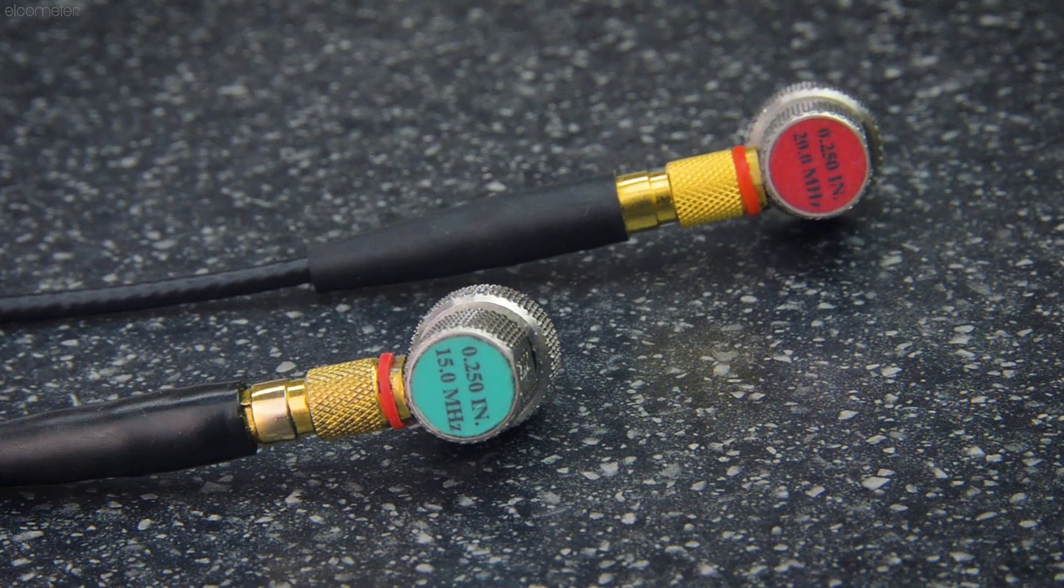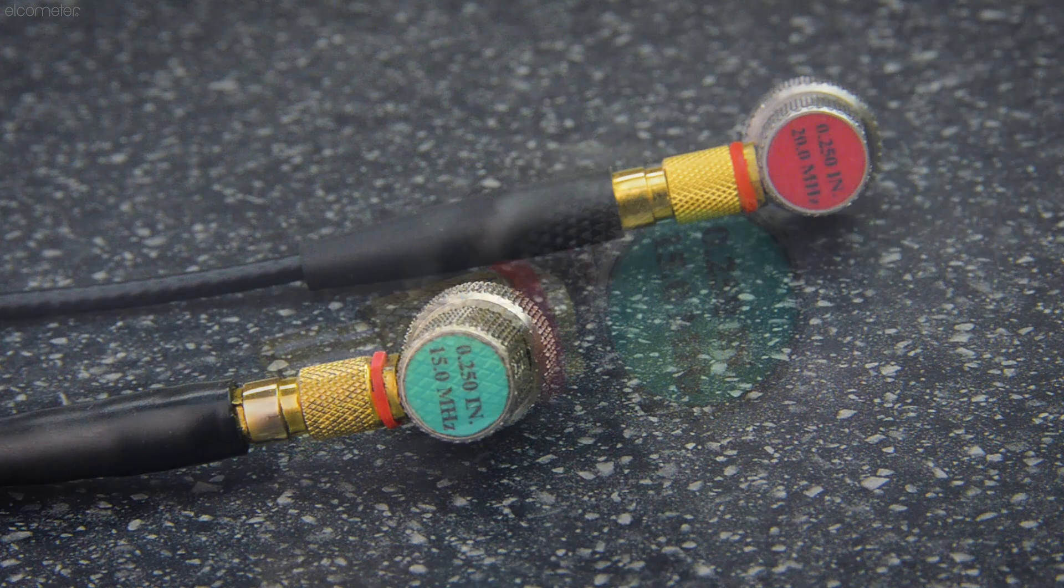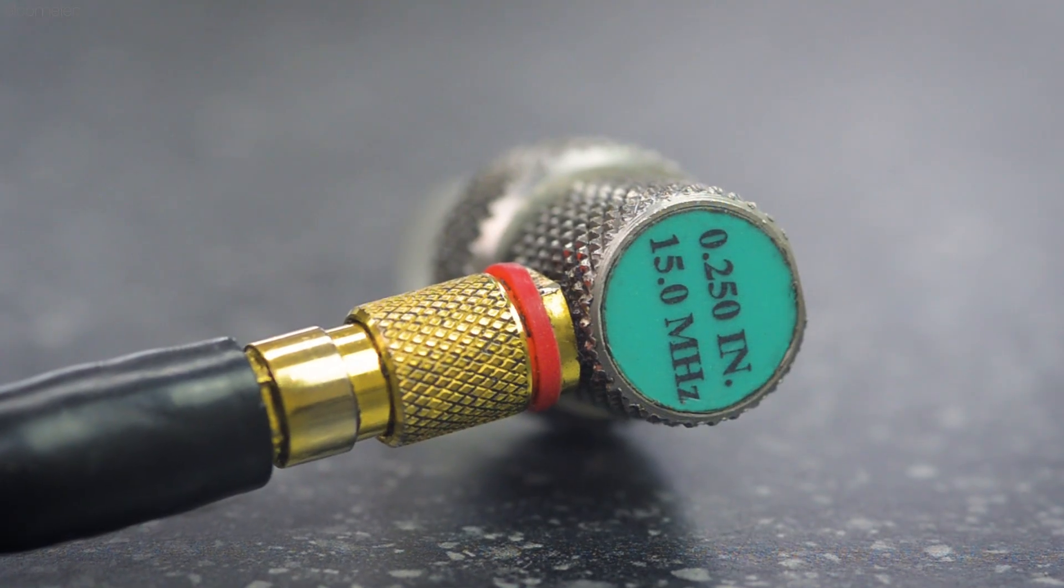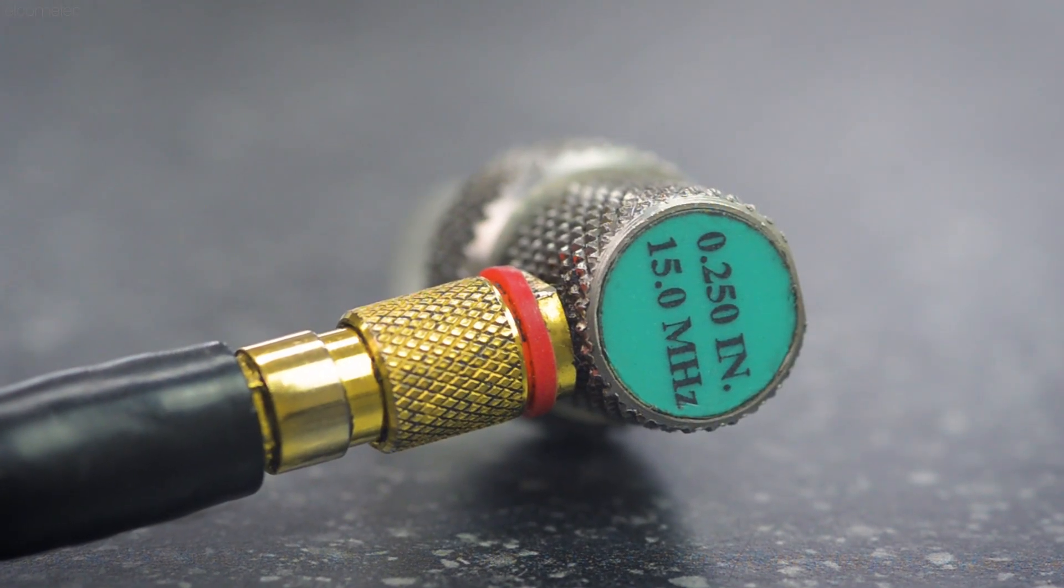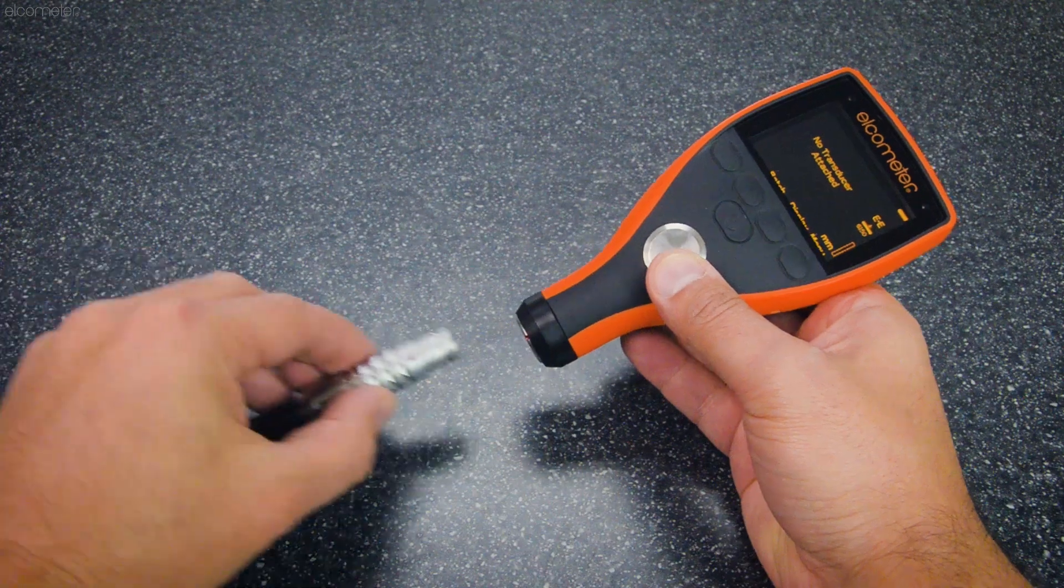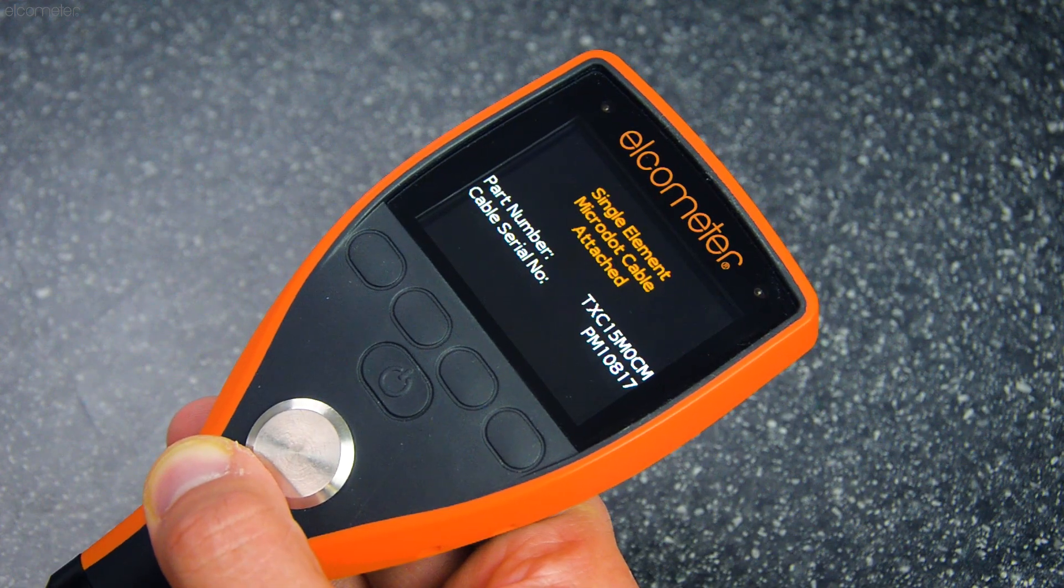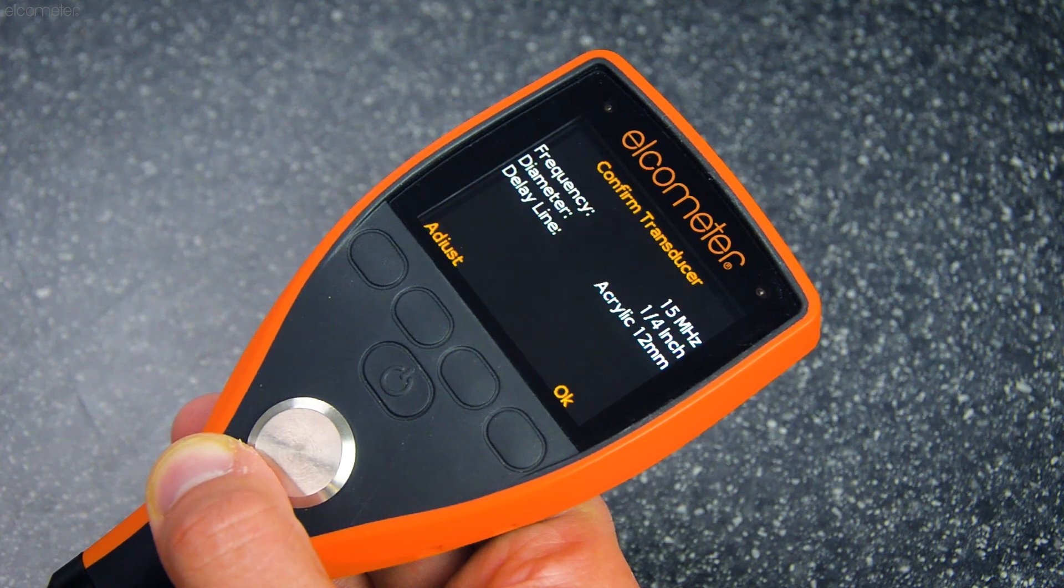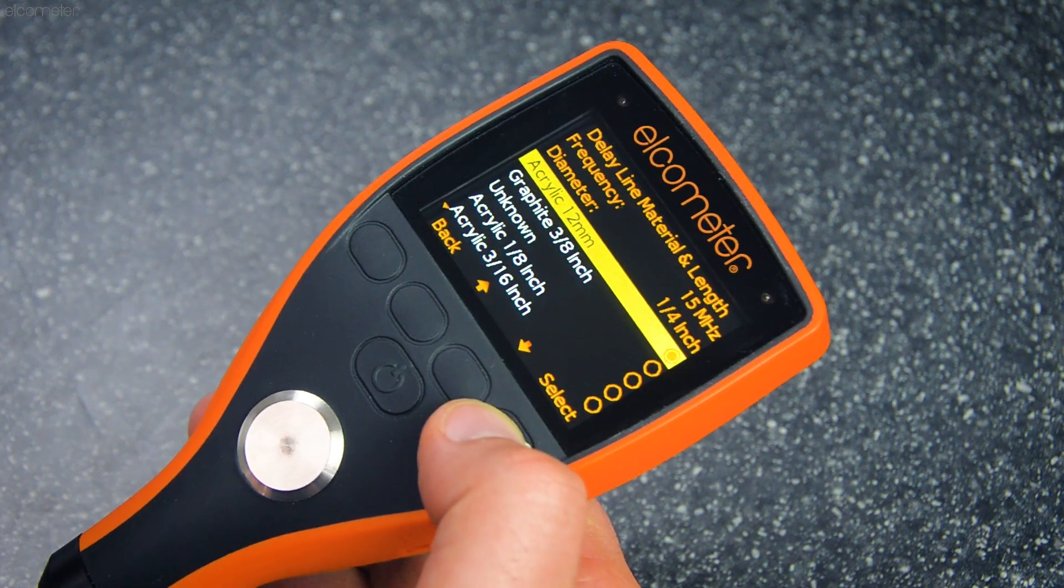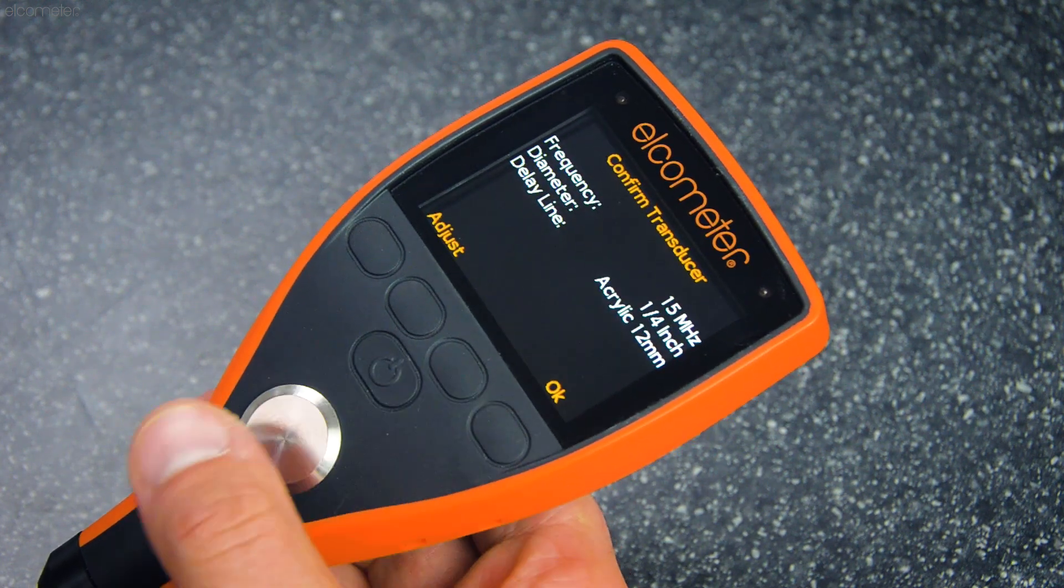The Elcometer PTG thickness gauges are designed to work with Elcometer's range of intelligent transducers, which all have automatic probe recognition. So as soon as the transducer is connected to a gauge, it immediately detects what type of transducer you're working with. All you need to do is set the appropriate length and material of delay line.